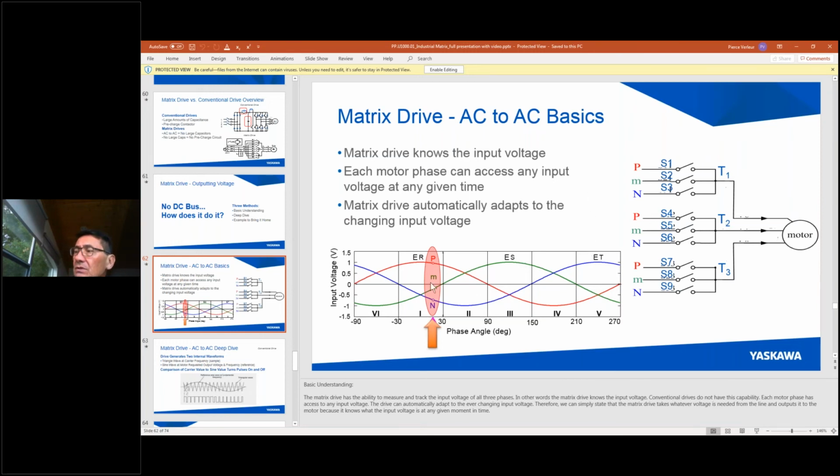So the ability to choose more than one voltage height at any given moment, as opposed to only having the option of 700 volts, means we, at some points, will still put in full span voltage to the motor. So we will hit the motor with a 700 volt pulse, but at most other times we're less than 700 volts. With that said, the argument could be made that we don't need as much of a filter. And do we need a filter at all for the voltage spiking? Because this voltage spiking issue is death by 1,000 pinpricks, and therefore if we're hitting the motor with 2,000 full voltage 1,400 volt spikes versus 100, the motor insulation will last longer, obviously, in the case where we have a lower cumulative number of high voltage spikes.